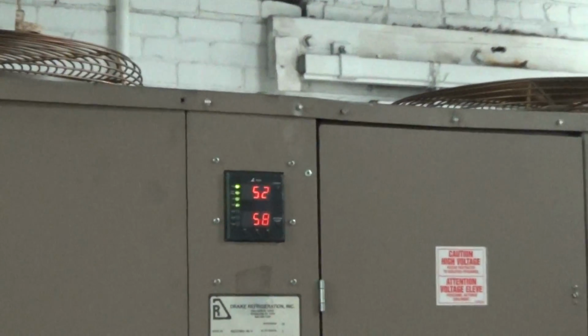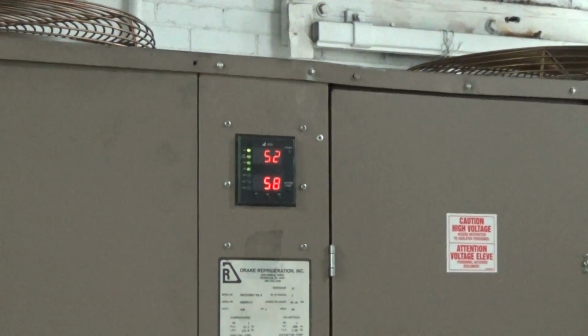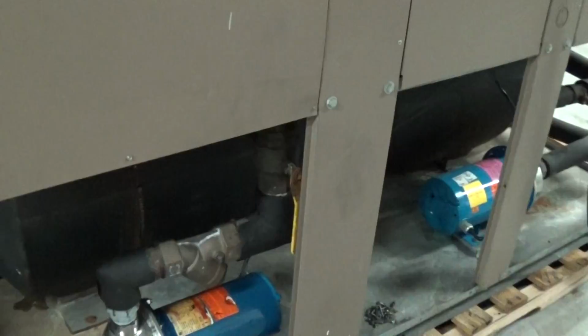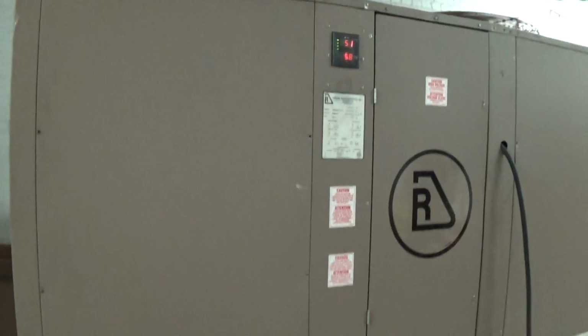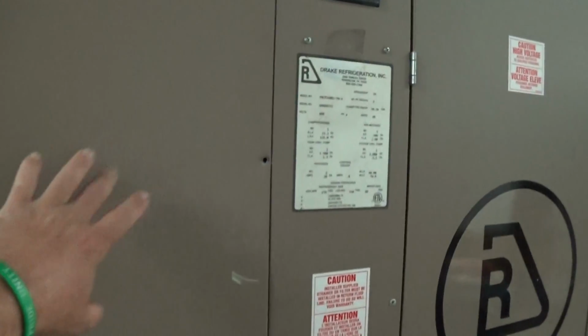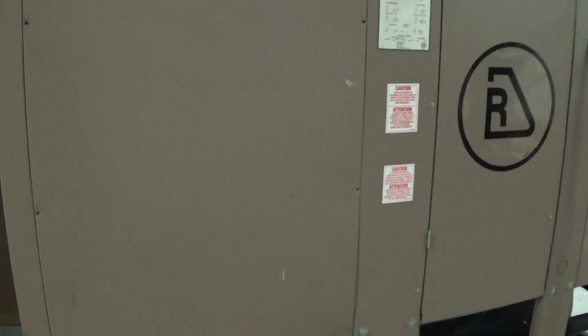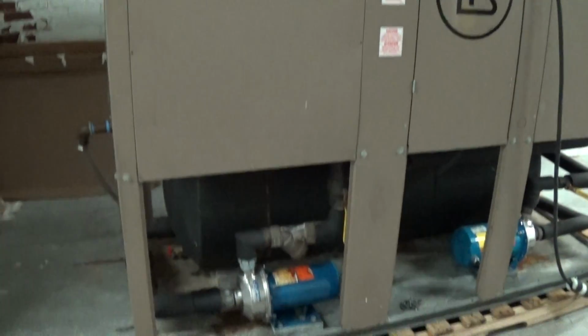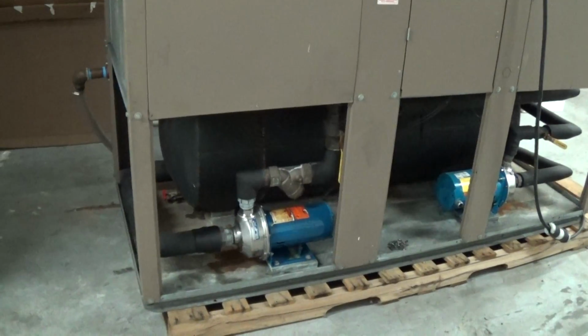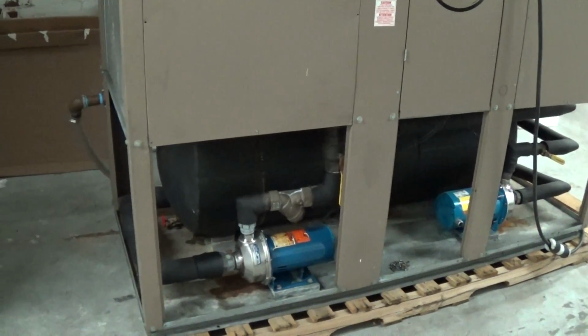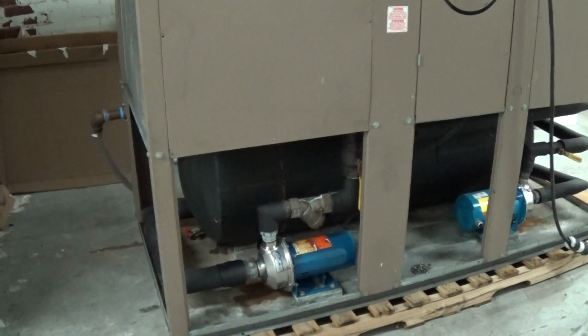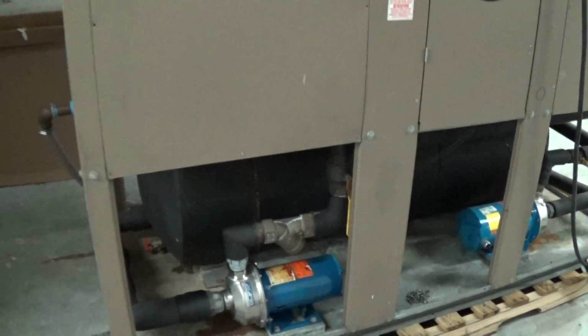But while we're waiting for the first compressor to shut off, one note here again is this shut off valve here. We can close that just to demonstrate how the flow switch works. These have a pretty high-end flow switch behind this door here. It actually senses the differential in the water pressure in two different locations. In some cases you may have to adjust that a little bit. If you're confused on it, just give us a call. But we think we got it adjusted pretty well.